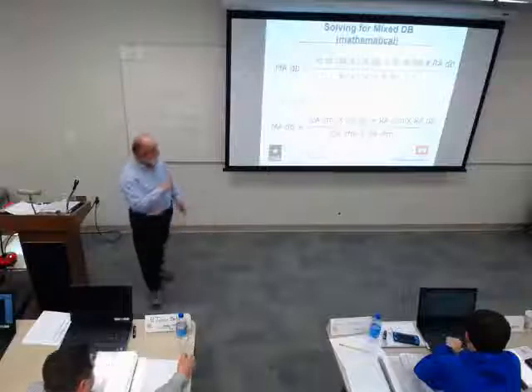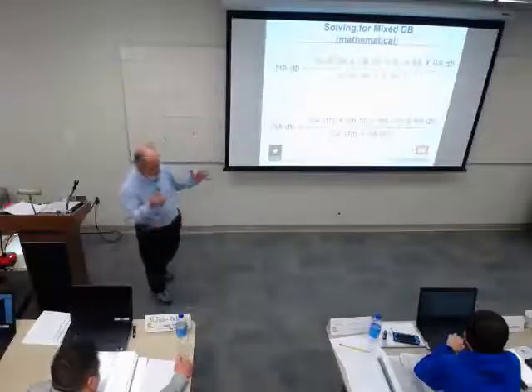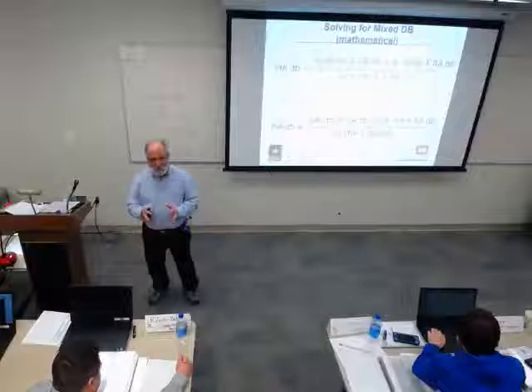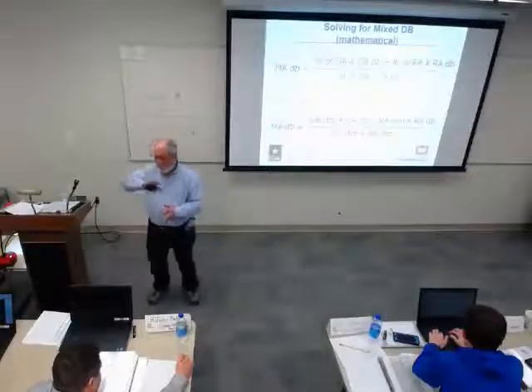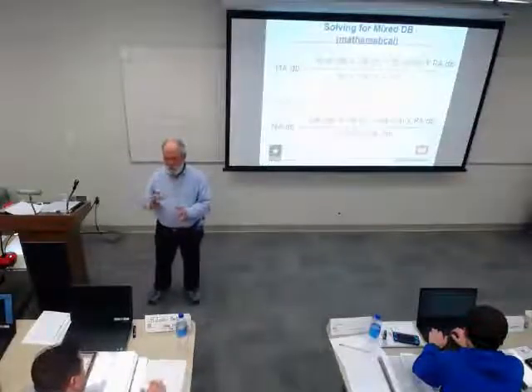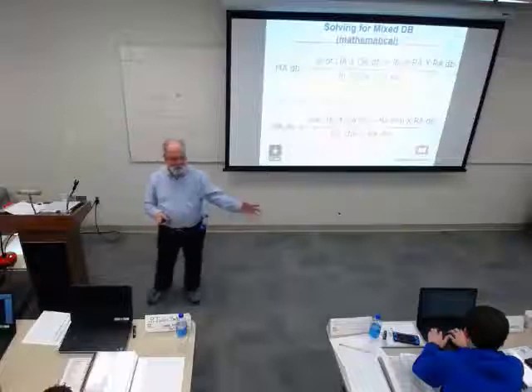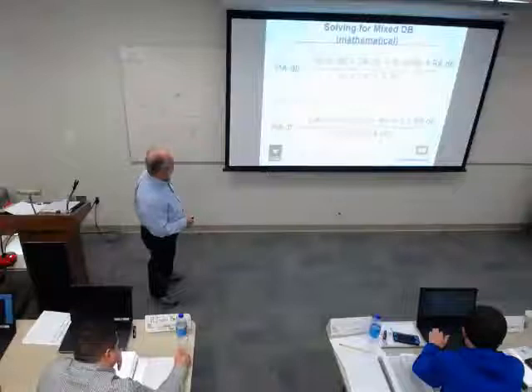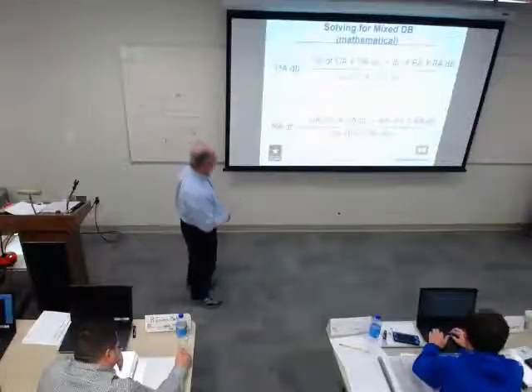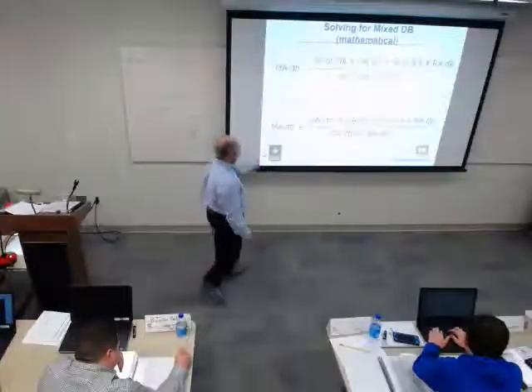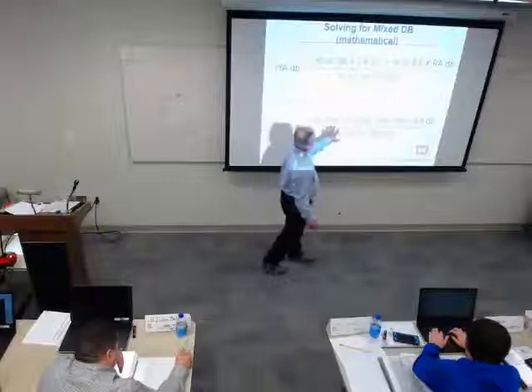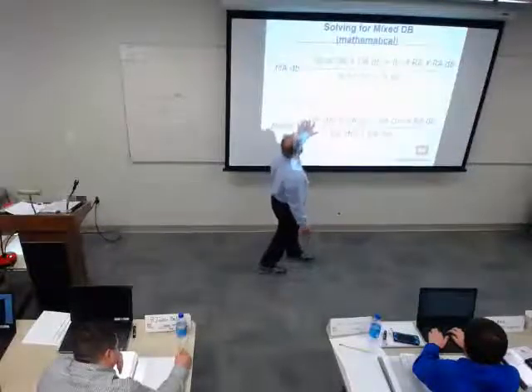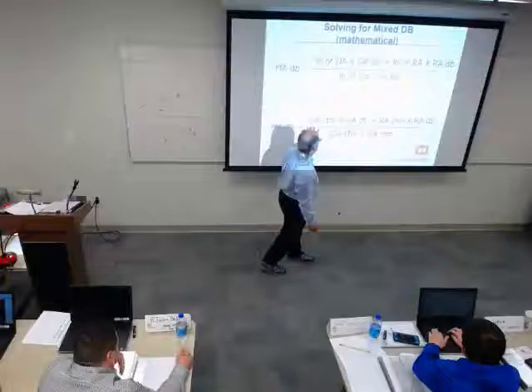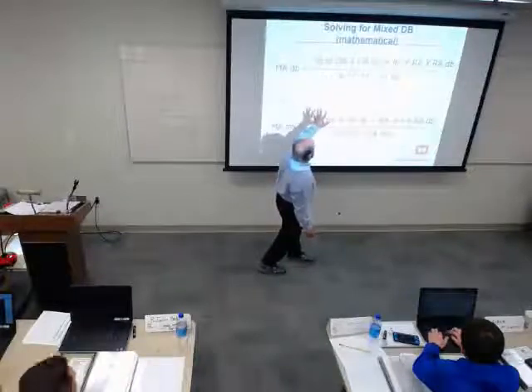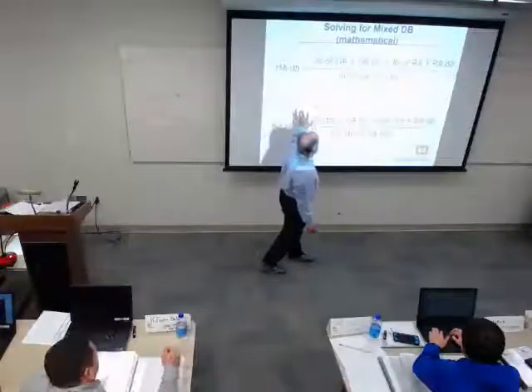Okay. Now in this case, we're going to start with masses. So mass of one, mass of the other. We know now what the mass is. We divide that number we just got, from multiplying temperatures times mass, and we get the average, which is our mixed air temperature. And here's how we convert from pounds mass to CFM. We multiply the outside air CFM. Okay, so it's converting from pounds mass to CFM. Okay. And we'll start with mass up there. I don't know why we start that, but we did.